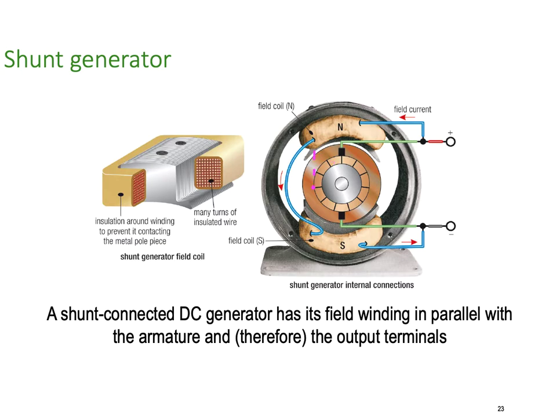So we need a tiny little bit of residual magnetism left in the machine to start to build the magnetic field. It only takes a few seconds, but you need a little bit of residual magnetism across the field, and then a little bit of voltage generates a little bit of current, and then the current just keeps building and building until the generator is up and running and you've got lots and lots of flux, and the armature itself is providing current to the load, and it's providing all this current to the field. So that's called a shunt generator.